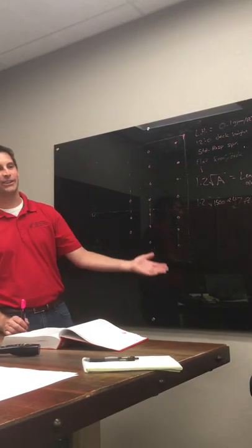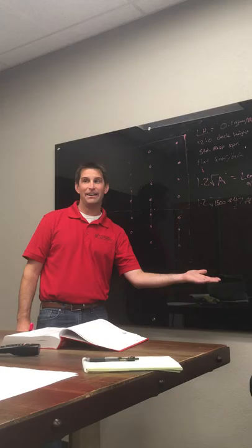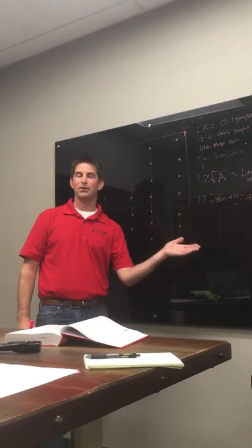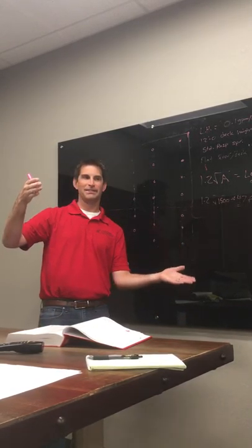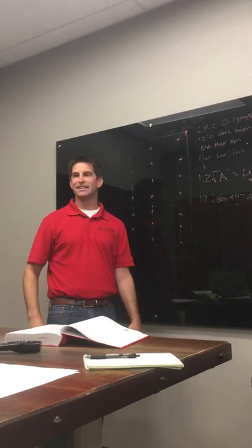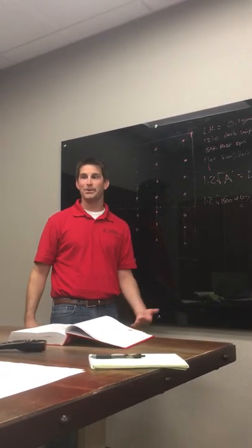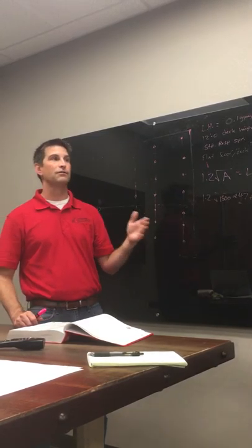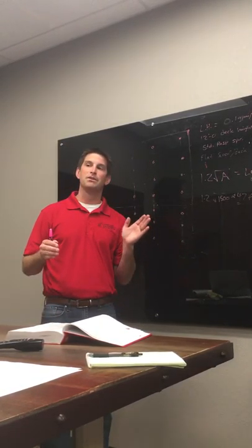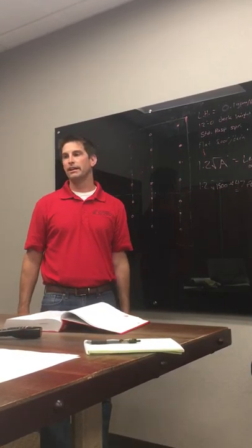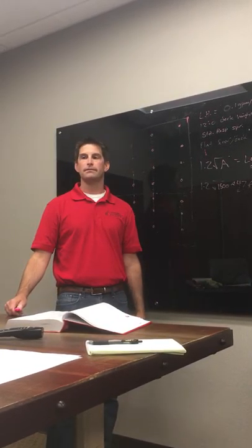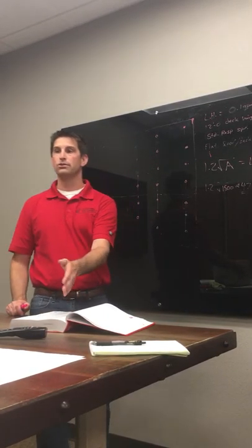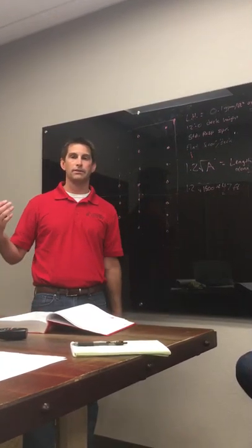You're totally right, because you're like, okay, well then what tells you a standard response at 155 should go off faster than a 175 quick response, right? Yeah, because it's standard. But it's all in the testing and listing, and it is very, very minimal. Even from what I've been taught and heard from some of the manufacturers, the difference in time between temperatures is like fractions of seconds between a 155 and a 200 degree head. It's so minimal that it's not even all that much. And they've actually started allowing you to use 200 or intermediate degree temp heads in all light hazard interchangeably, whether you want to do that, no difference.